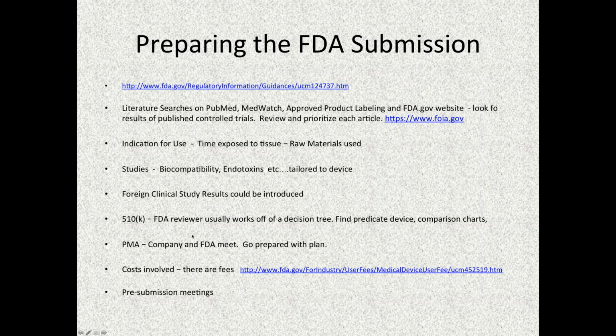Okay, under the 510K, the FDA reviewer works off the decision tree, finds a predicate device, and uses comparison charts. For the PMA, the company and the FDA will meet. You'll have to get with them because they have PMA coordinators, and you'll have to go prepared with a plan. Don't let them tell you what you need to do. Go there and say, this is what I intend to do, and then defend it. There are fees associated with this, and there's the ability to do what are called pre-submission meetings if you're concerned that your 510K or your PMA evidence plan is not sufficient.